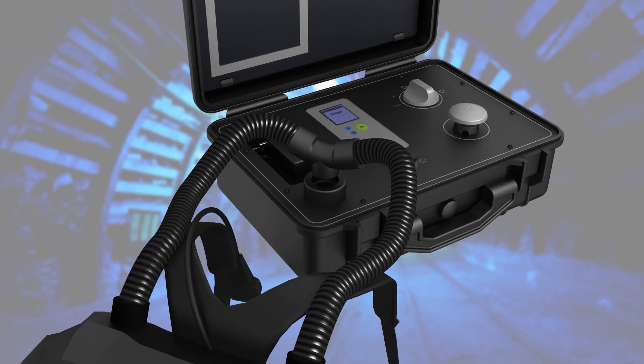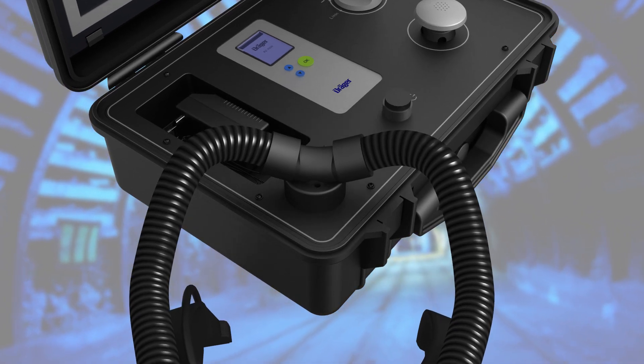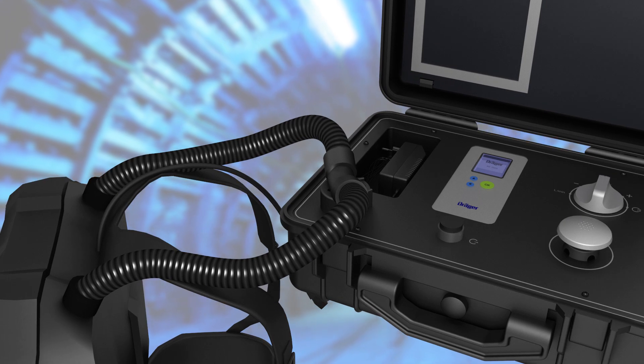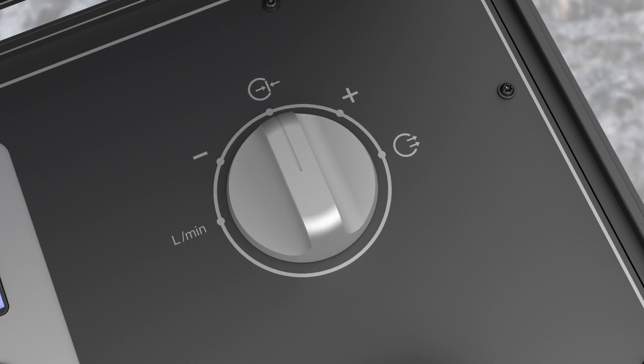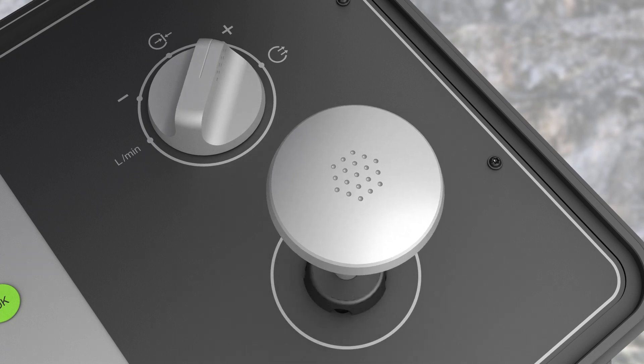The click adapter safely connects the BG4 to the test device. No need to detach it during the process as a new quick venting mode is already integrated. The whole procedure is further simplified by a manual switch which offers individual modes for each testing step, saving you time and effort.